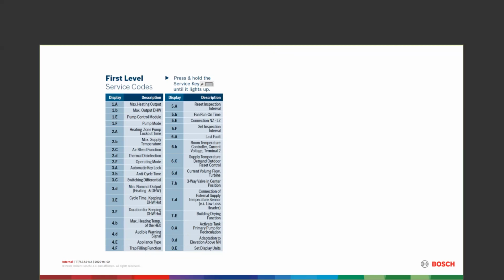A few other things. 6A, pretty well used for me, is last fault. That's going to tell you what fault code it might have been, an E9, EA, D3, D5. Depends on which fault was there. So you'll be able to find that. 6B we don't use too much. That's the current voltage for room temperature for terminal 2. That's your thermostat connection. Supply temperature demand outdoor reset control, we don't use very often on that one.